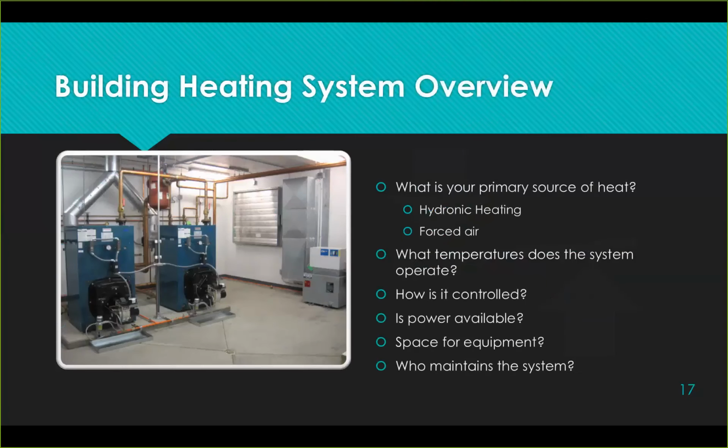So what about your building heating system? We either have hydronic heating or forced air in most of our community buildings. Hydronic heating, if we're going to be using cooling jacket water, we're bringing it over. Hydronic heating is a much easier tie-in than possibly forced air. What temperatures does the system operate? It's really important to consider holistically what your building heating system is. If you don't know how your system is being operated, you don't know if the heat available is even going to be something you can take advantage of.